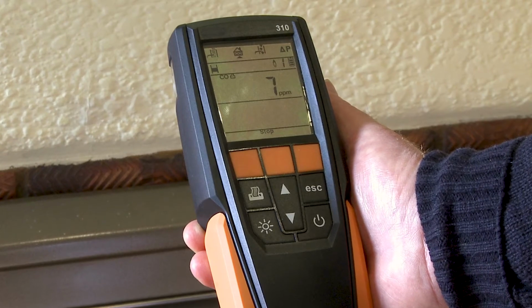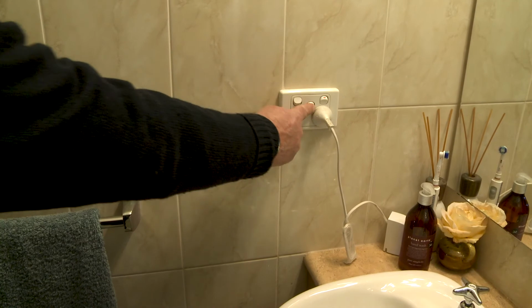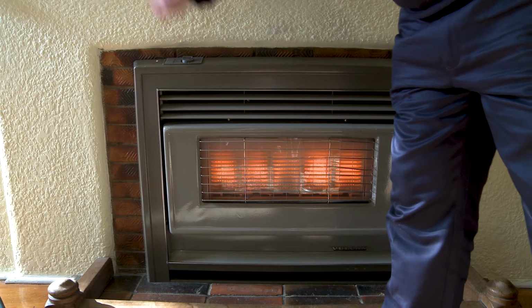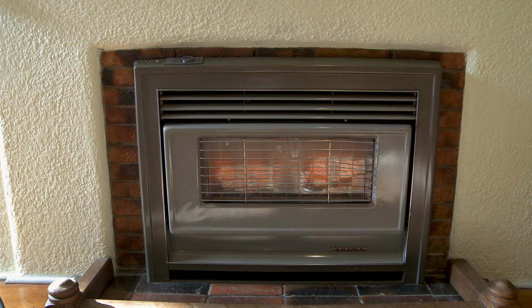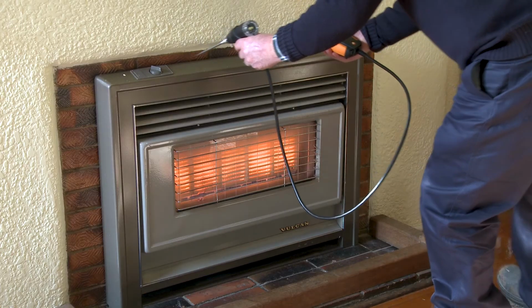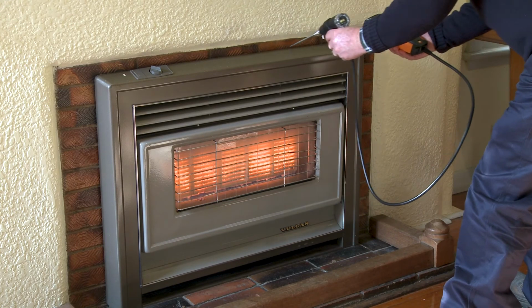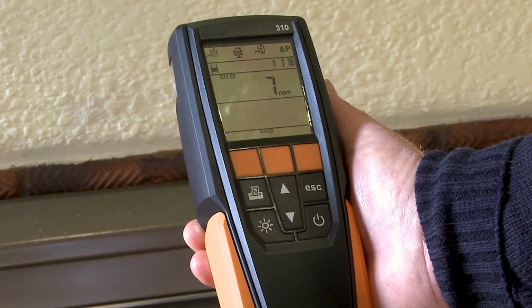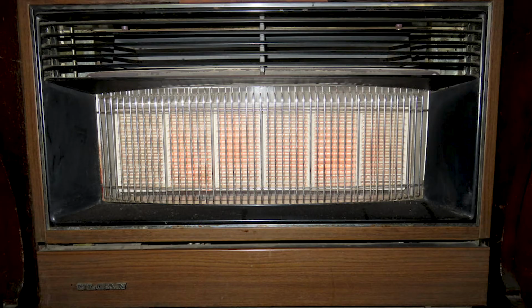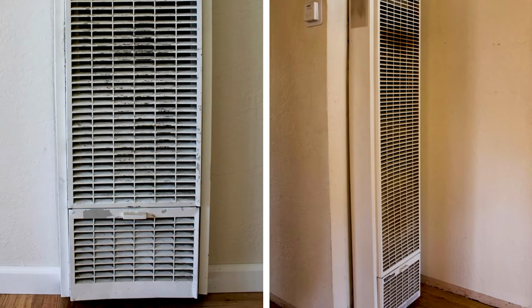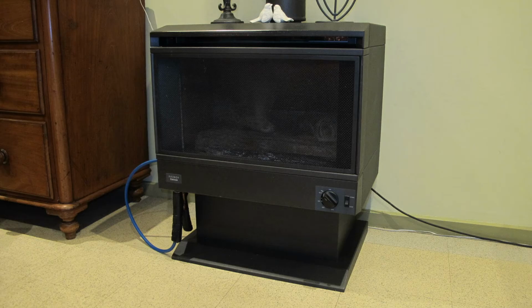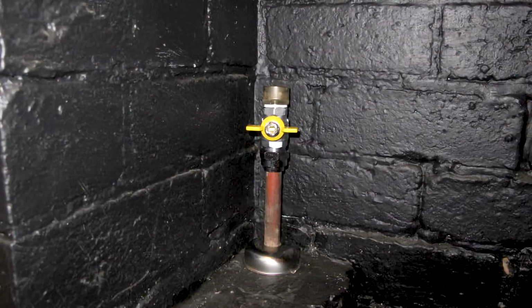If CO spillage is detected, you will need to switch off all exhaust fans and the appliance. Wait a few minutes and then restart it without the effect of a negative pressure environment and run the entire spillage testing process again. If there is still spillage recorded, check for faults with the appliance or flue. If faults can't be fixed, then the appliance must be made safe by isolating it.